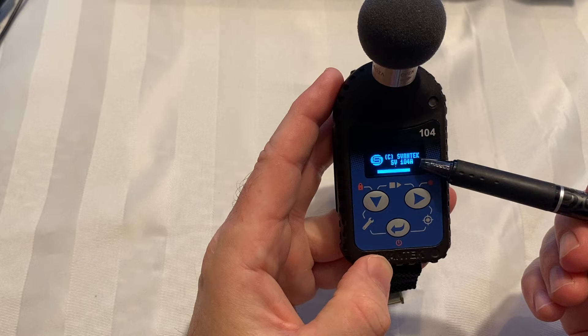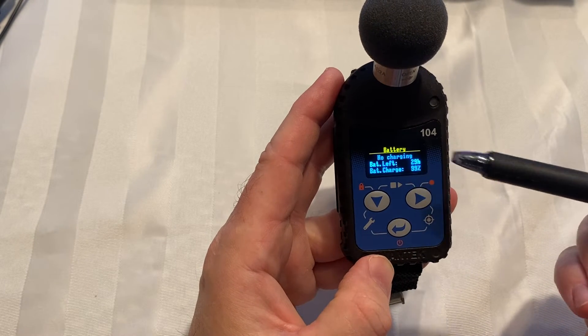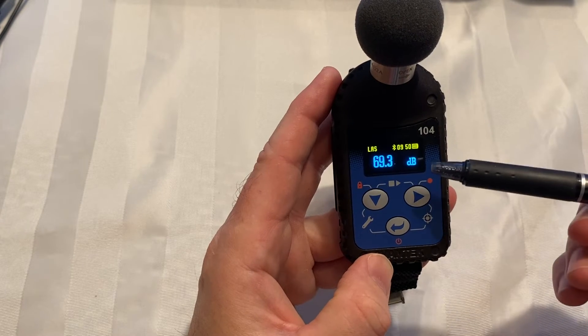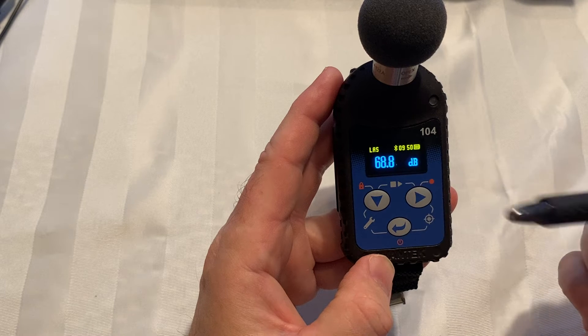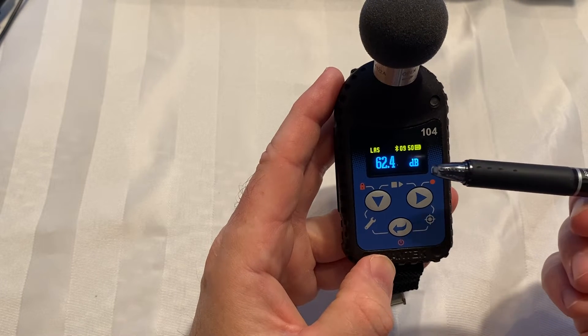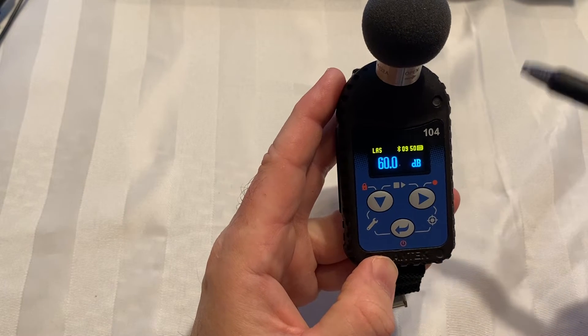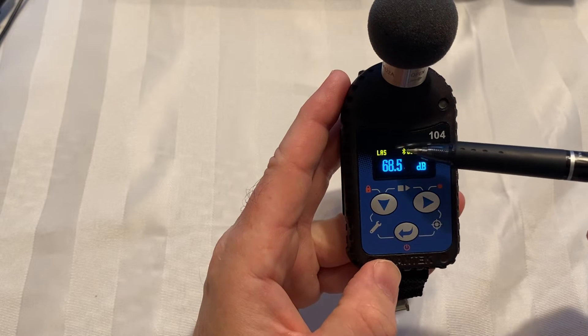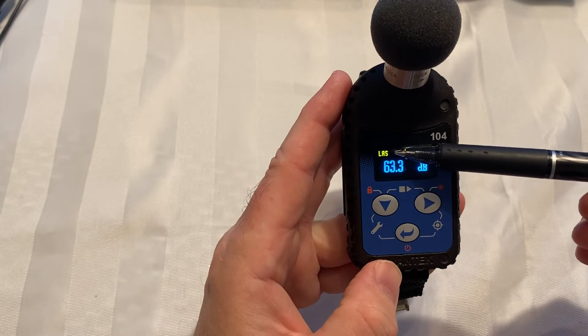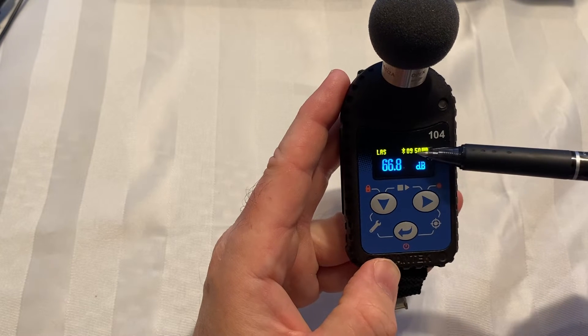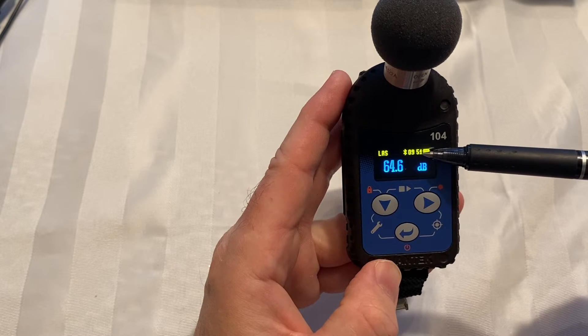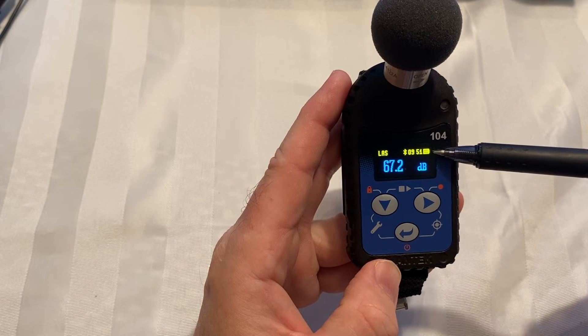It's booting up the settings. I've got this one set up for one profile, which was ACGIH, and it gives details of the battery and things like that. Then in this case I've got it set to measure sound or noise in real time. On the display you'll see - and this is all selectable in the software - I have it measuring L noise with an A filter, slow. This other symbol is for Bluetooth, which is turned on.